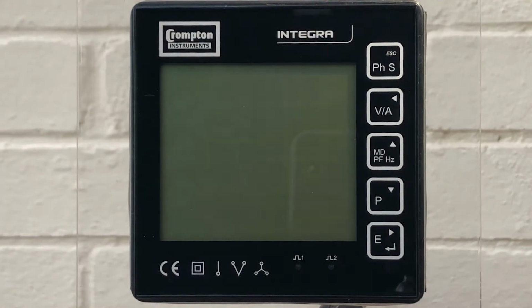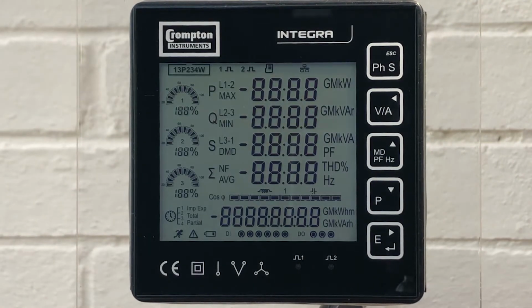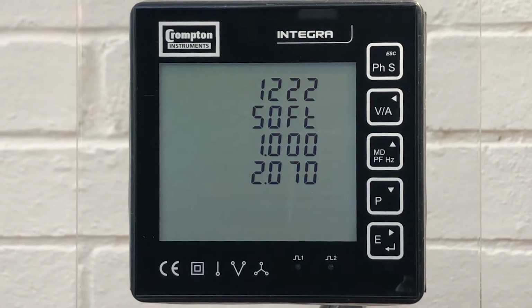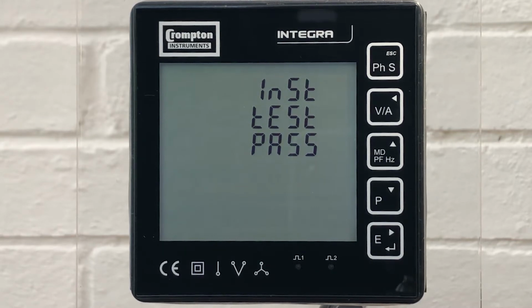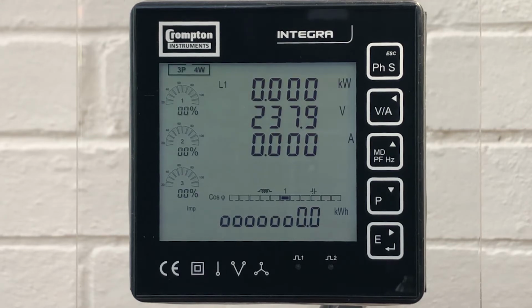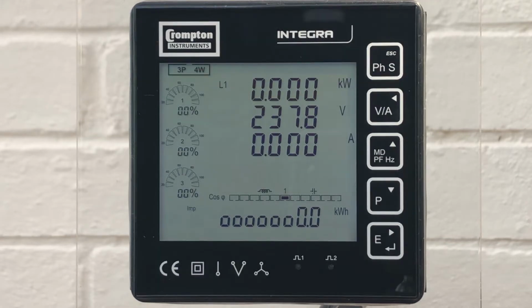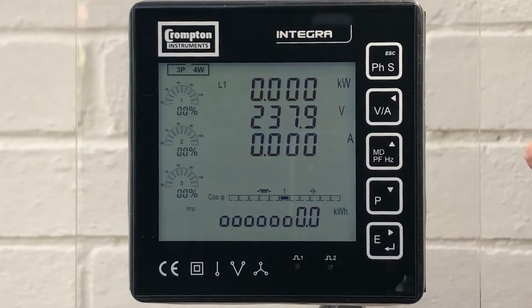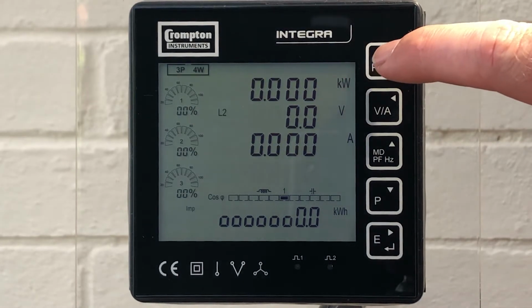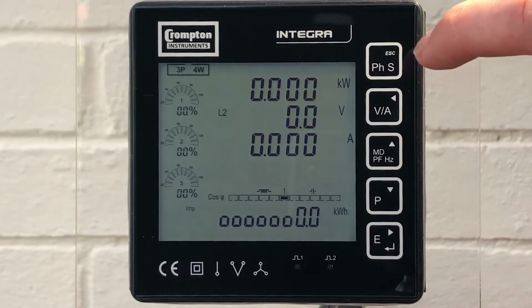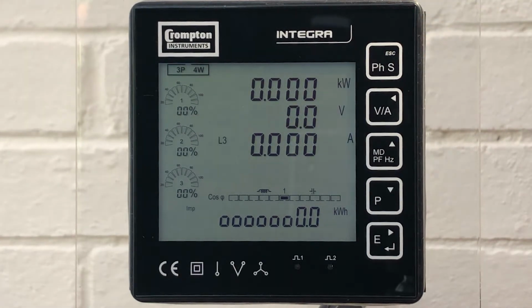Now we're going to view the measured parameters of the Integra 1222. On power up, the Integra checks the display segments, displays the latest firmware revision installed, and indicates that it's passed an internal self-check. The top button selects the power, voltage, current and energy of the active system. The first screen shows phase 1, so we're going to press the top button once more to show phase 2, and then phase 3, power, voltage and current. Another press of the top button returns us to the first screen.